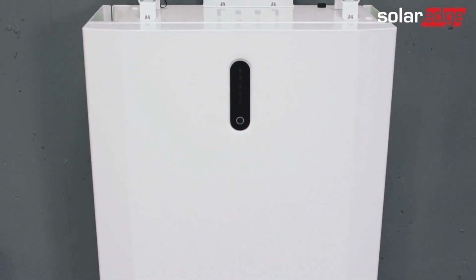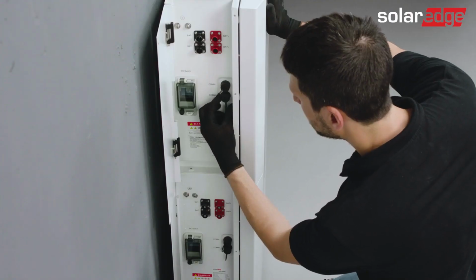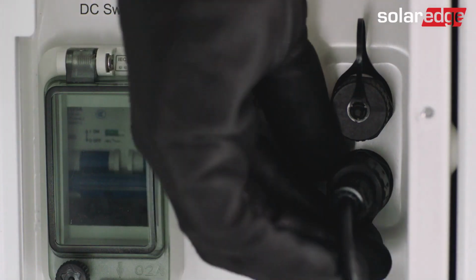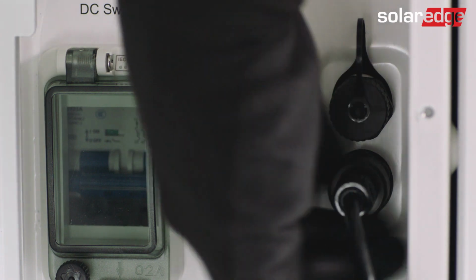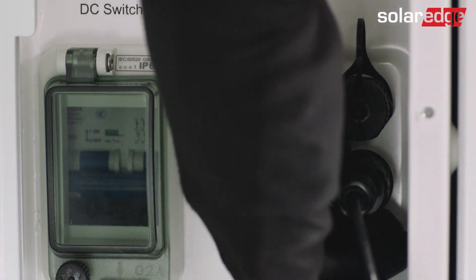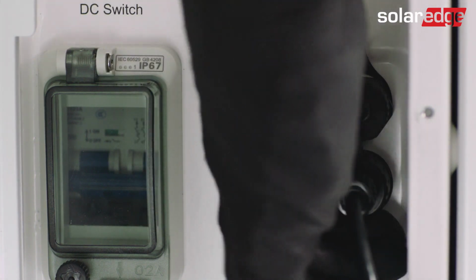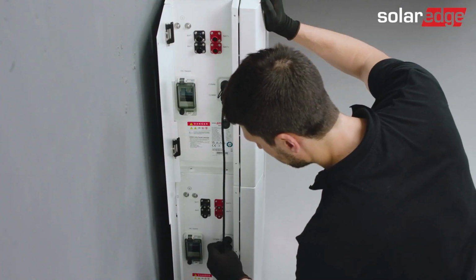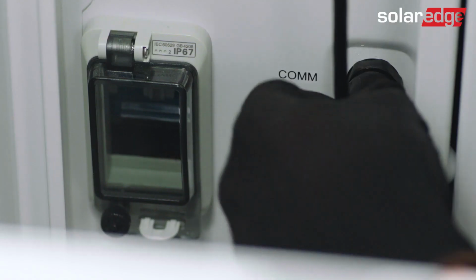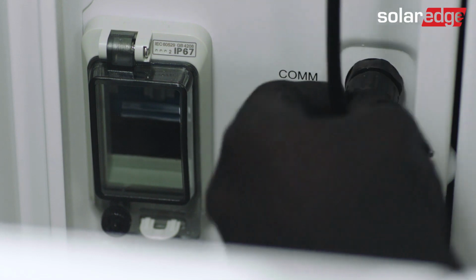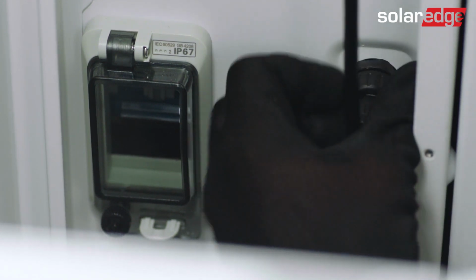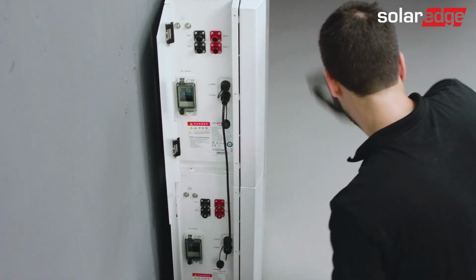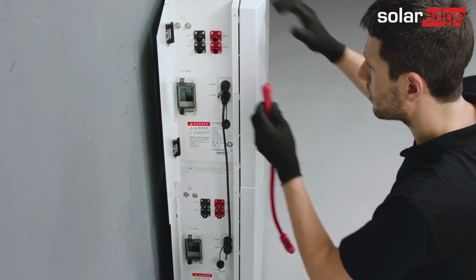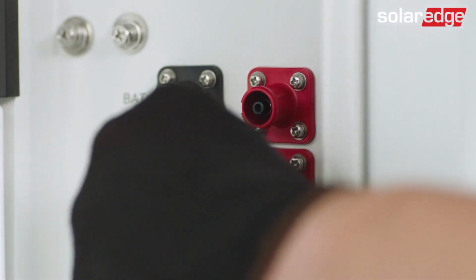Now let's start connecting the cables between the batteries in the first tower. The first cable will be the communication cable on the 2 batteries tower. Assemble it between the bottom communication connector of the upper battery to the upper communication connector of the bottom battery, and secure the cable once it's connected. Make sure the communication cable is secured along its length, and tighten it first by hand without using tools. If it doesn't screw easily, please unscrew it and try again.